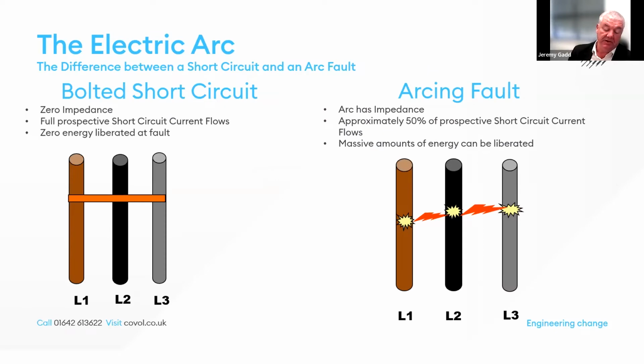Some of you might be wondering if there is any difference between a bolted short circuit fault and an arc flash, and the answer is yes. With a bolted short circuit, there's zero impedance and the full short circuit current flows with no energy liberated at the fault. In an arc flash, the arc has impedance and around 50% of the short circuit current will flow through the fault, delivering an enormous amount of energy as depicted in the previous image.